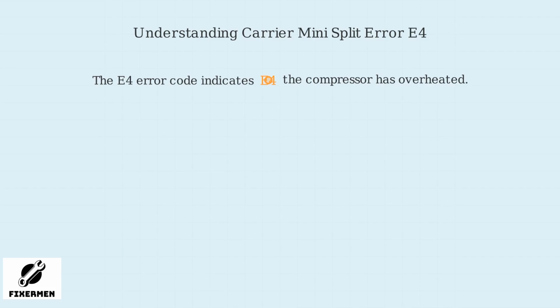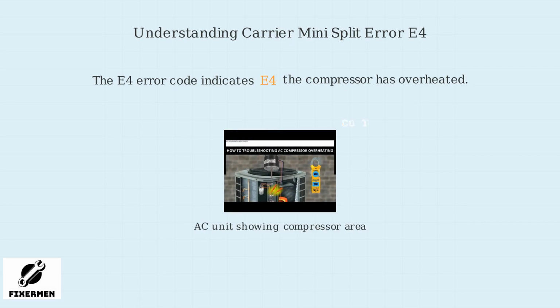The E4 error code on your Carrier mini split indicates the compressor has overheated. This is a safety mechanism designed to prevent damage to the compressor. The compressor is a vital component in your mini split system. It's responsible for circulating the refrigerant throughout the unit.